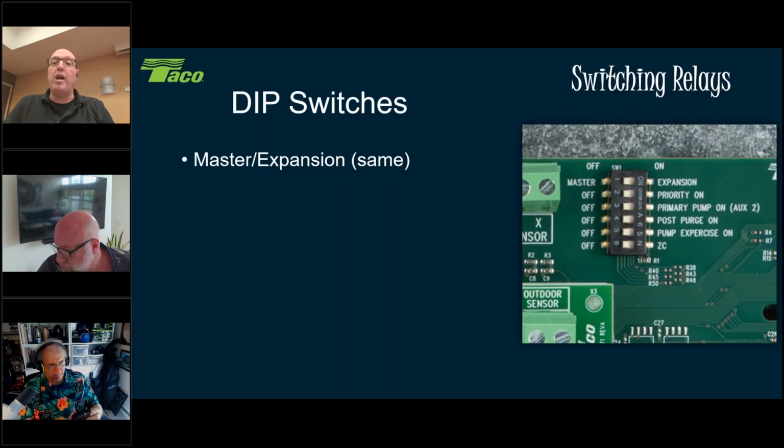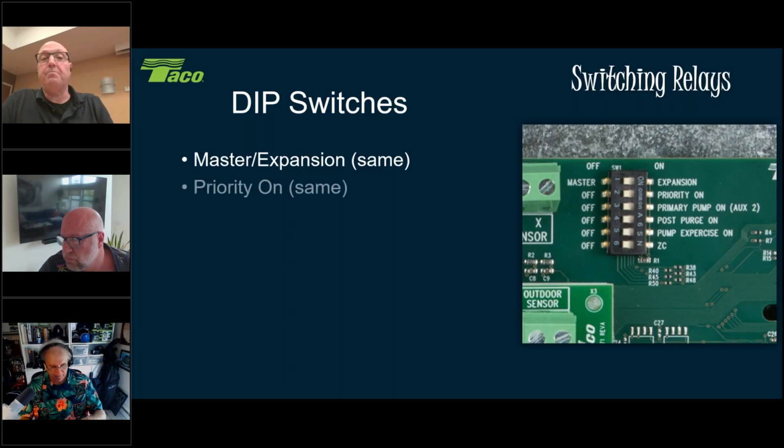Now, I just want to make sure everybody knows this. When you look at the dip switches and you'll see the on-off labeling here, on-off doesn't necessarily mean off, right? It's just another function to it. Does that make sense? I've got a live audience here too at the same time, so I want to make sure they know that, and everybody here online knows that as well. It's a separate function sometimes. So master means, if you're not using that daisy chain, then you leave them all in the master switch.